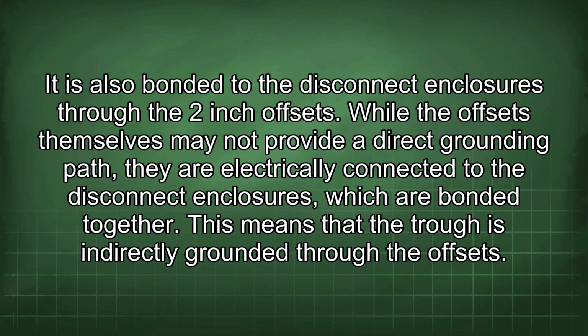It is also bonded to the disconnect enclosures through the 2-inch offsets. While the offsets themselves may not provide a direct grounding path, they are electrically connected to the disconnect enclosures, which are bonded together. This means that the trough is indirectly grounded through the offsets.